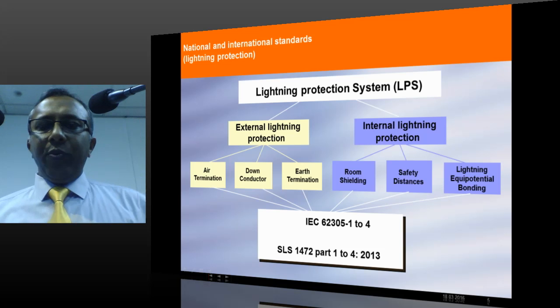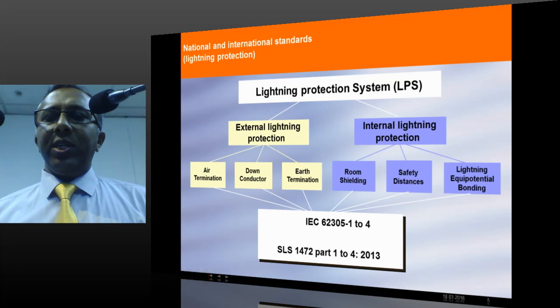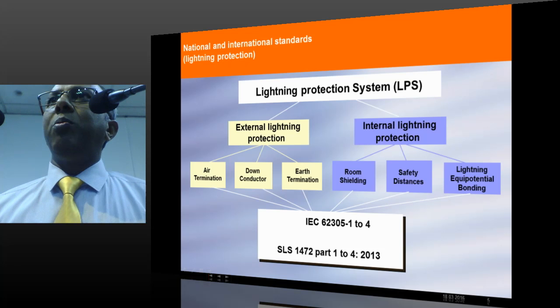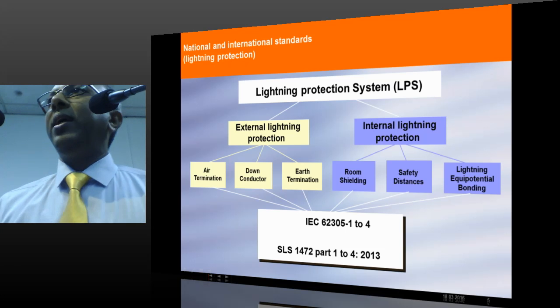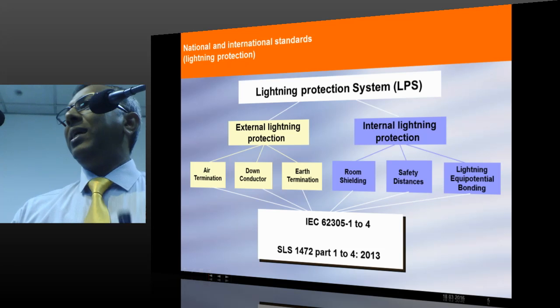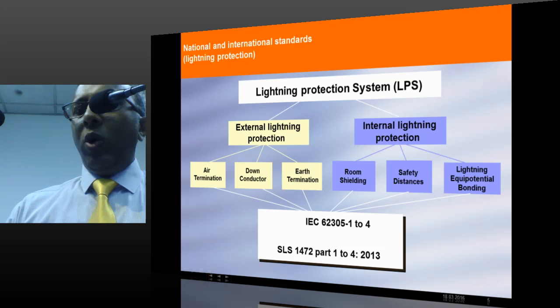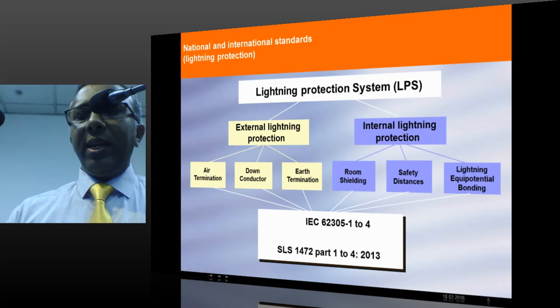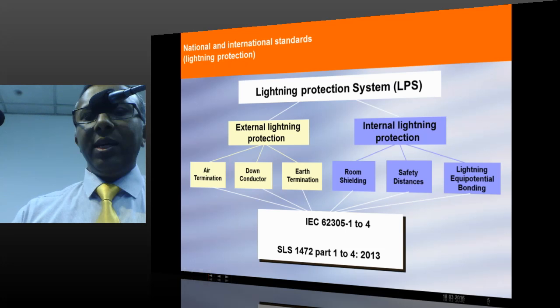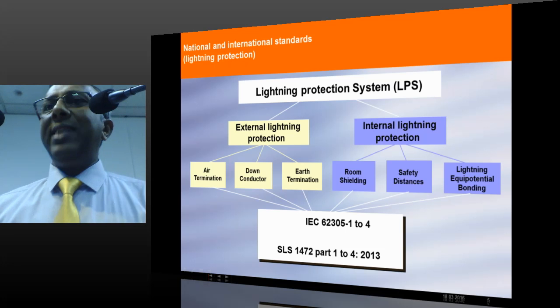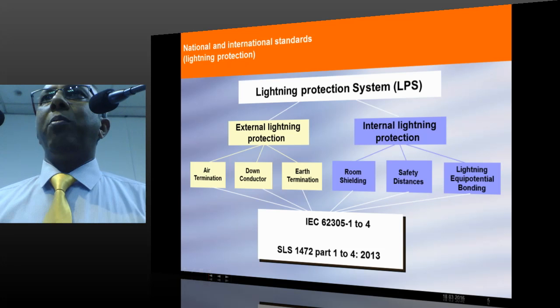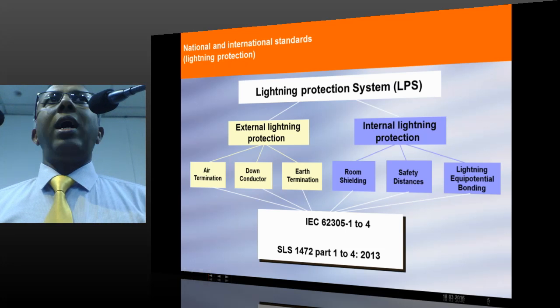The same way, internal lightning protection. Internal lightning protection talks about protecting electrical and electronic equipment inside the building. When we talk about protecting electrical and electronic equipment inside the building, these 3 points, room shielding, safety distances and lightning equipotential bonding, are all important.